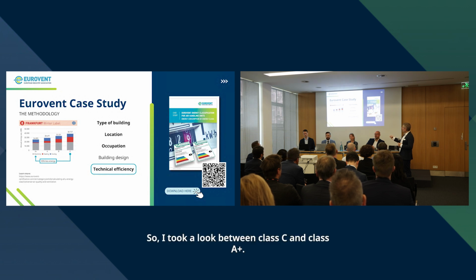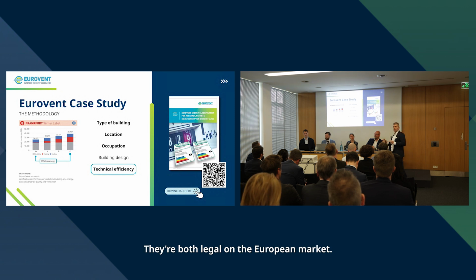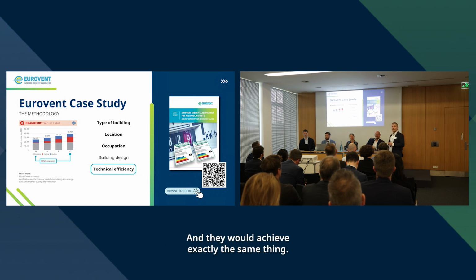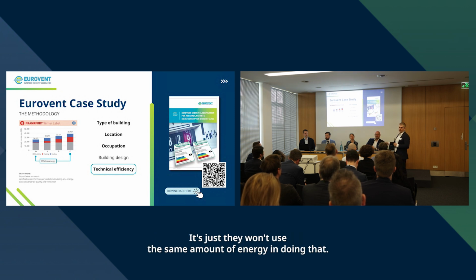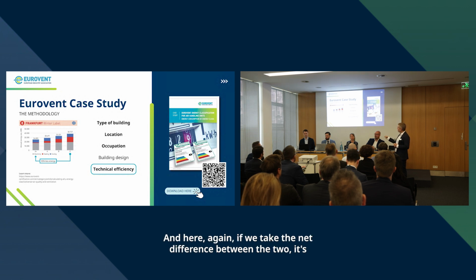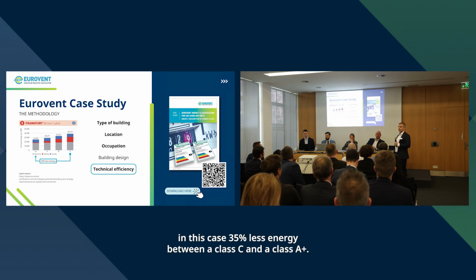So I took a look between Class C and Class A+. They're both legal on the European market—you can sell them both, and they would achieve exactly the same thing. They will get the air into the building, they will do heat recovery. It's just they won't use the same amount of energy doing that. And here again, if we take the net difference between the two, it's in this case 35% less energy between a Class C and a Class A+.